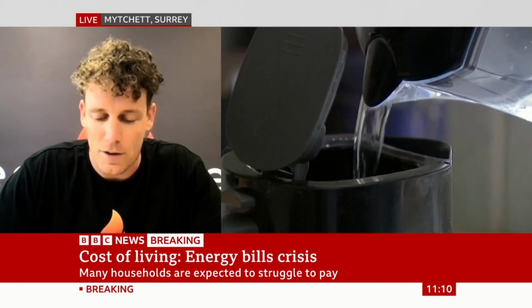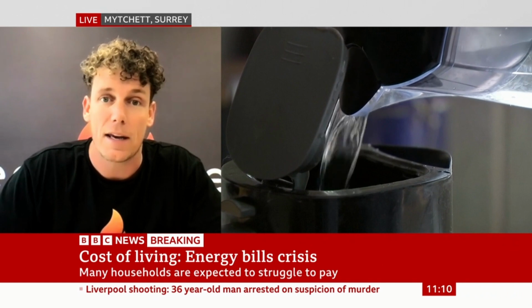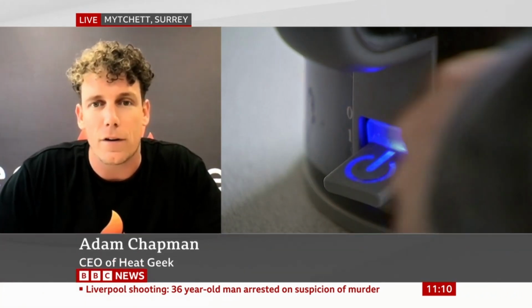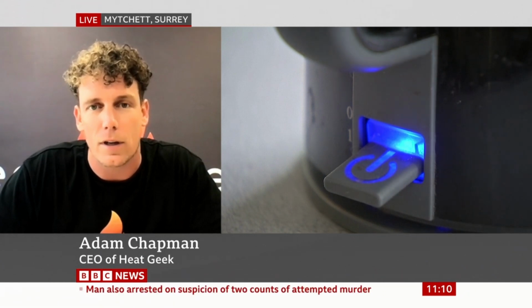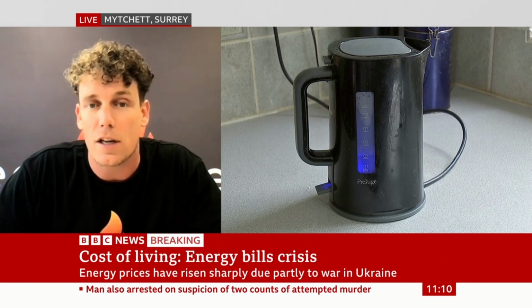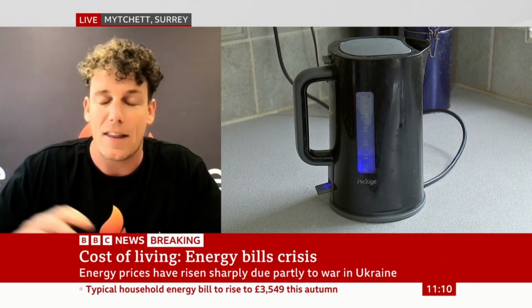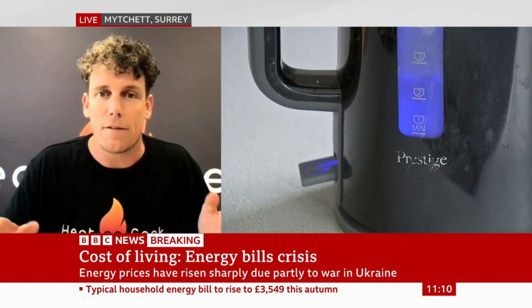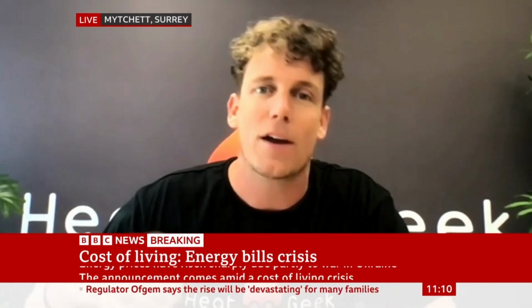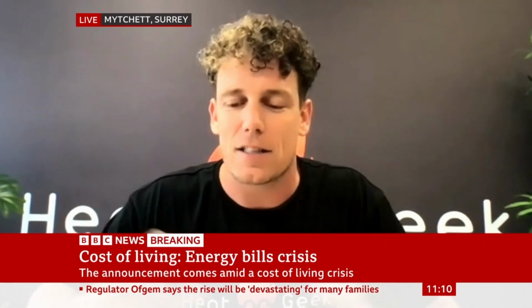Yeah, okay, so we do have practical tips. First would be to turn your boiler flow temperature down. Usually on the front of your boiler, you'll have a little dial that will indicate the flow temperature that comes through your radiators. You really want to try and turn that down as much as possible. Now, again, there are issues here. For example, if you have a boiler that has a separate hot water cylinder, you can't turn it down too low or you won't get hot water. So there's little caveats like that.